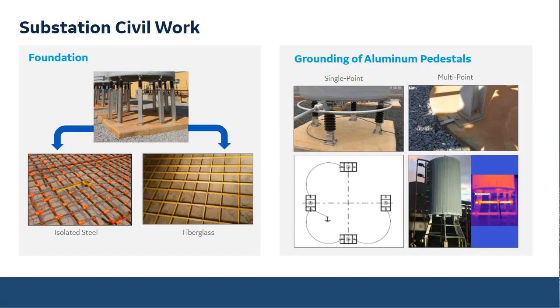The main issue that we notice is how the concrete pads are designed. It's common to see customers considering regular steel rebars, which is okay, but we would need to add some spacers between the coil and the ground if there is vertical clearance. If you cannot have spacers between the reactor and the coil, we could use different solutions, for example adding some type of insulation material between rebars, or, worst case, using a fiberglass type of reinforcement on the base. On the very right-hand side of this slide, we see a thermal scan of a reactor, and we can see a closed loop.